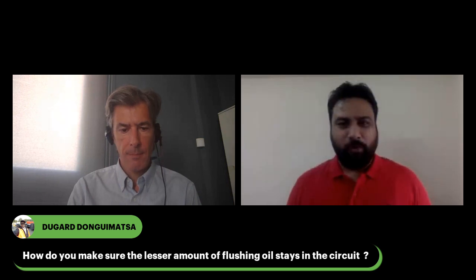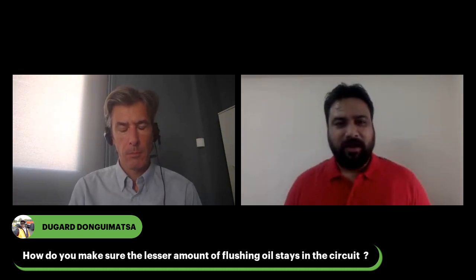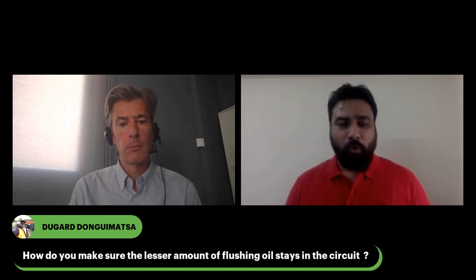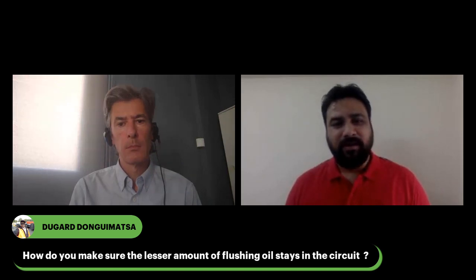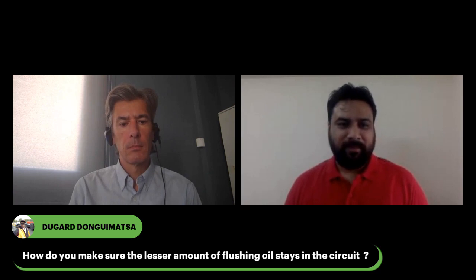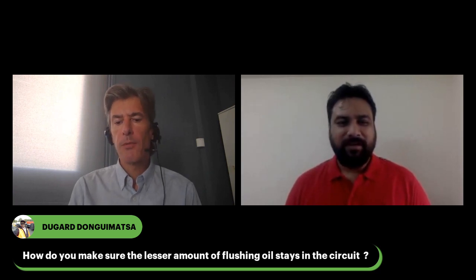The choice of flushing oil is compatible with the lube oil system oil you are actually going to pour in tomorrow. So that's the first step you need to take while selecting the flushing oil. But if you want the entire flushing oil removed, nitrogen purging is an option you can adopt. In your flushing loops, you need certain points or ports where you can purge the nitrogen from a good drain system, from where the flushed oil will come out, and you can collect it and dispose of it, or reuse it for another system. I hope that answers your concern.